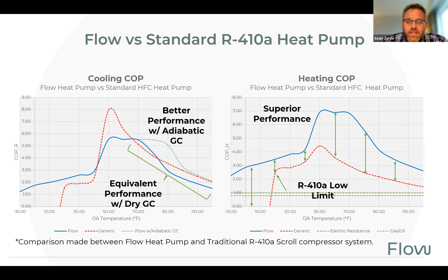Now looking at a simultaneous mode, anywhere in that 50 to 70 degree window you see in the middle on the left here, open a window. That's your economizer mode. We really should just bring in some fresh air and make everybody happy. But outside of that mode, look at how much higher our blue lines and our dotted green lines are than a traditional dotted red line HFC system. You can really take into account really high temperatures and low temperatures and maximize your efficiencies across the board.